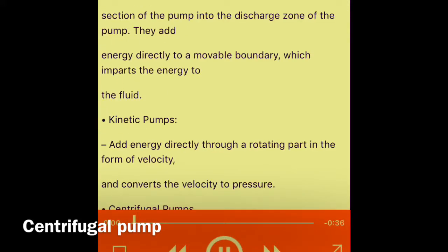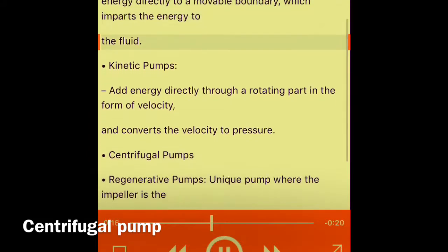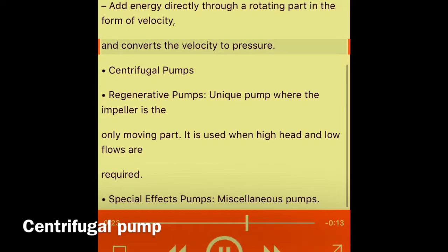Positive displacement pumps operate by forcing a fixed volume of fluid from the inlet pressure section into the discharge zone. They add energy directly to a movable boundary which imparts energy to the fluid. Kinetic pumps add energy directly through a rotating part in the form of velocity and convert the velocity to pressure.